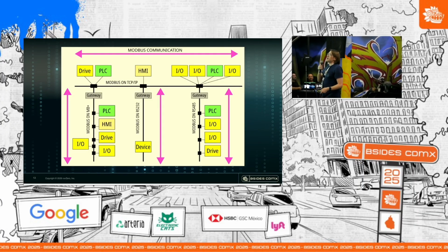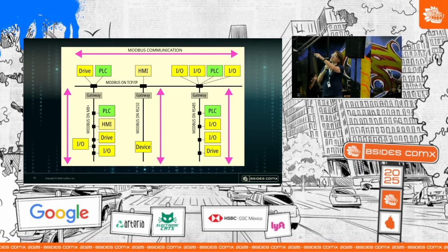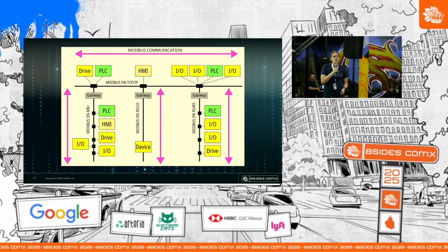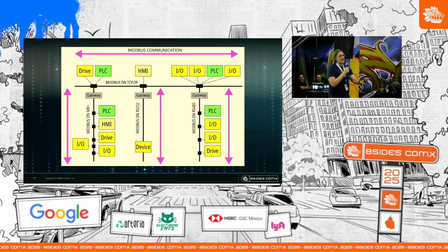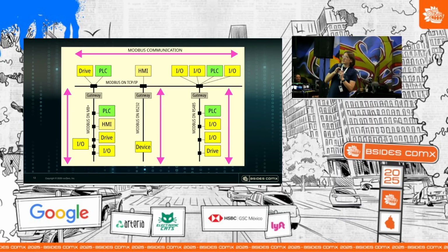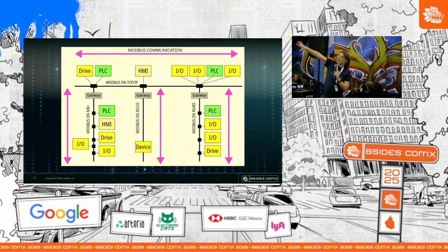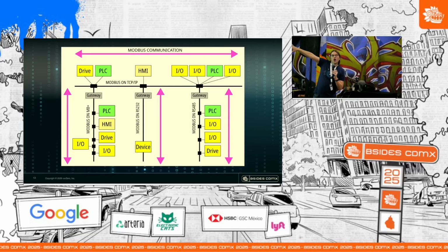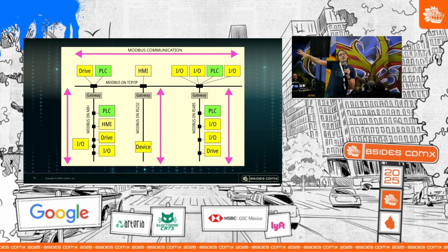And you can see that Modbus lets you control systems with a shared bus, right? A shared medium. And also it was physical medium independent. So you can see here on the left, it's talking over MB Plus, which is another shared physical bus. In the middle, you've got RS-232, and it can only talk to one device at a time. RS-232 is the old serial standard. It's not old, it is old, but it's also still the serial standard.